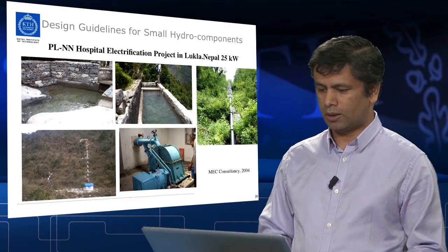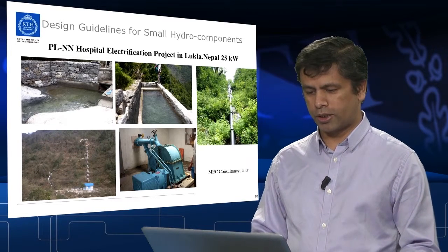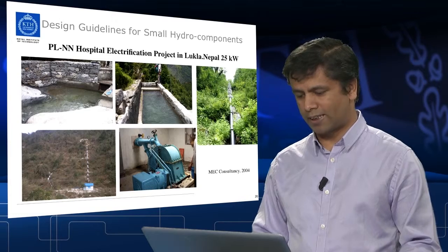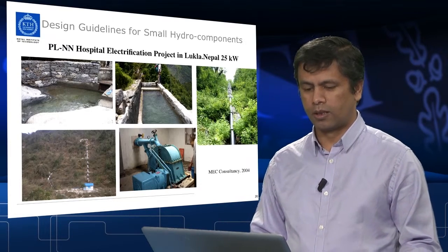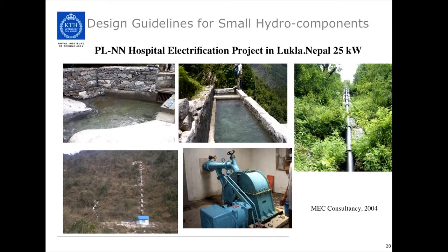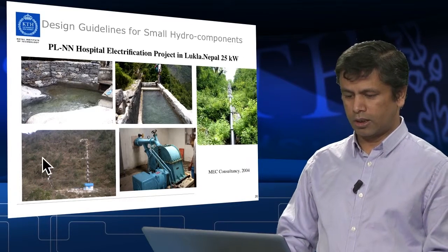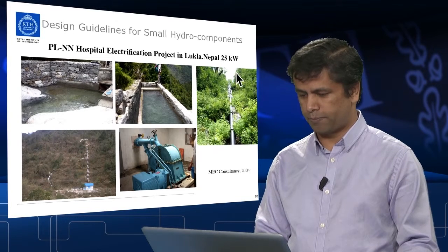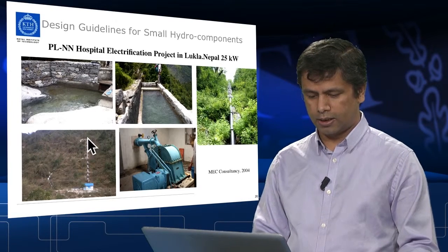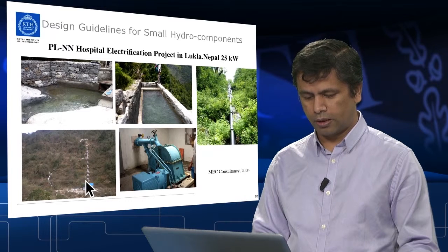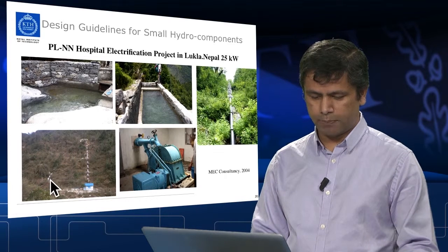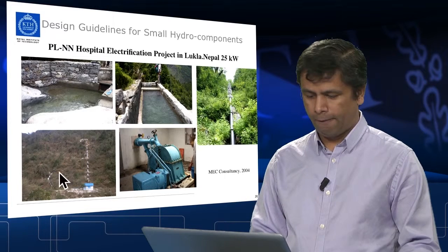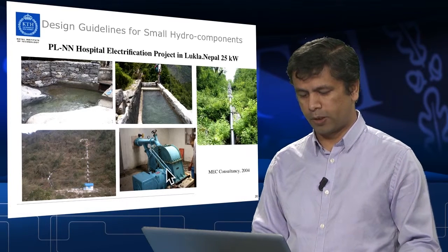You can see one of the projects that has been constructed, which I was engaged in 2004. This was the project for electrifying the hospital in Lukla in Nepal, a 25 kilowatt project. You can see the intake location, the forebay tank, the penstock pipe alignment along with the powerhouse, the spillway coming here, and the turbine coupled with the generator.